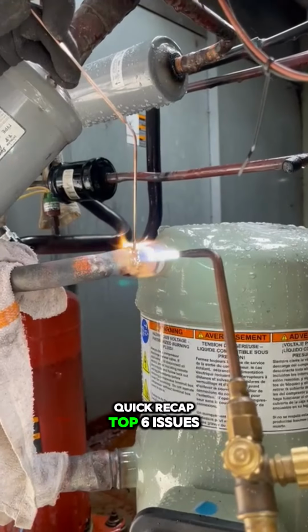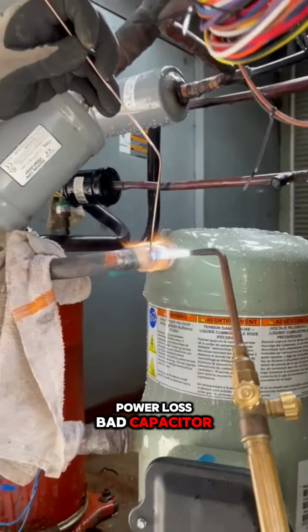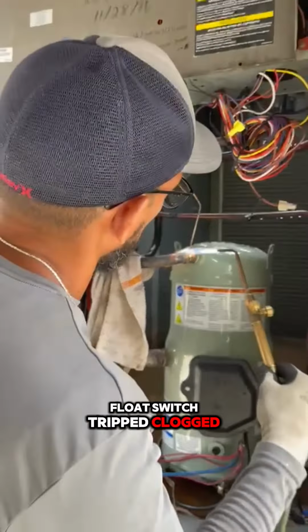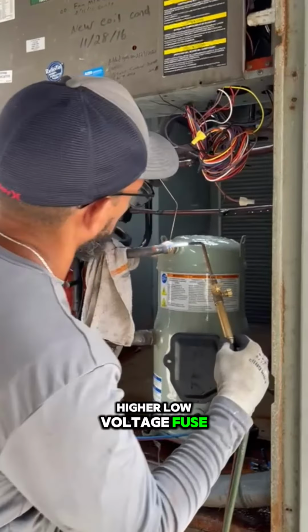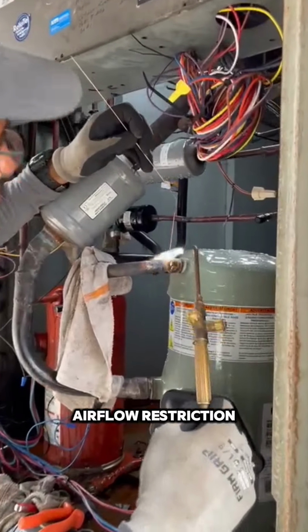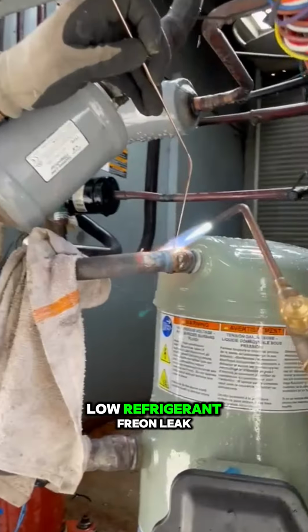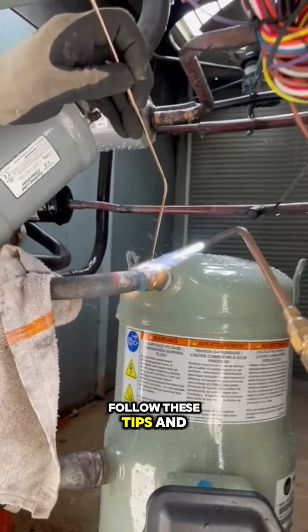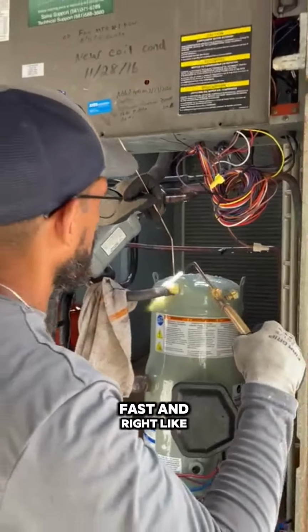Quick recap, top 6 issues: power loss, bad capacitor, float switch tripped, clogged drain line, high or low voltage fuse blown, dirty coil or airflow restriction, low refrigerant, freon leak. Follow these tips and you'll handle most no cooling calls fast and right.